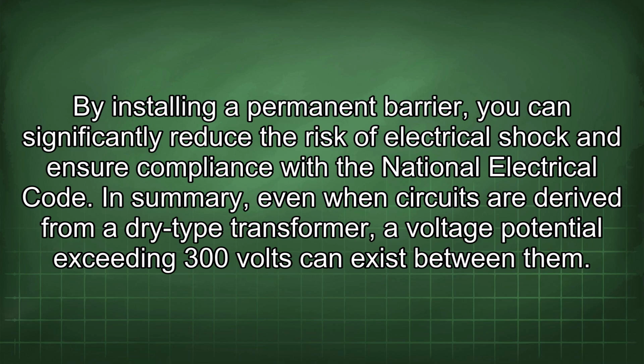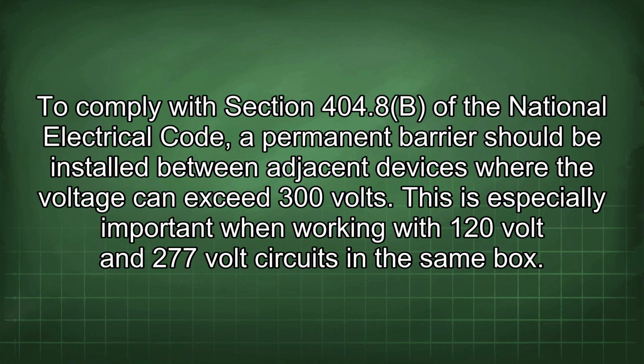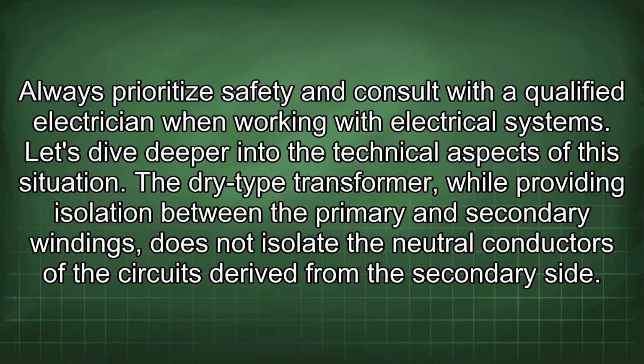In summary, even when circuits are derived from a dry-type transformer, a voltage potential exceeding 300 volts can exist between them. To comply with section 404.8(B) of the National Electrical Code, a permanent barrier should be installed between adjacent devices where the voltage can exceed 300 volts. This is especially important when working with 120-volt and 277-volt circuits in the same box. Always prioritize safety and consult with a qualified electrician when working with electrical systems.